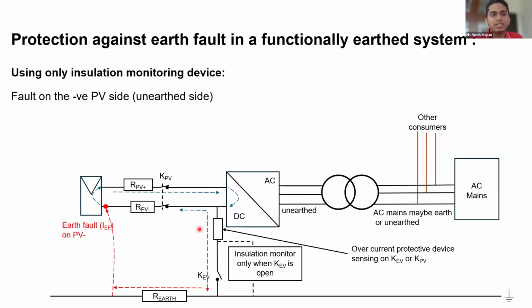But even in that case, the current which is flowing through this path will be really low, and if you have done proper equipotential bonding and all the other bondings properly, you won't be getting a shock. The only thing is, if the maintenance guy checks every day, then he'll be able to know that there is a fault in the system, and rectify it.